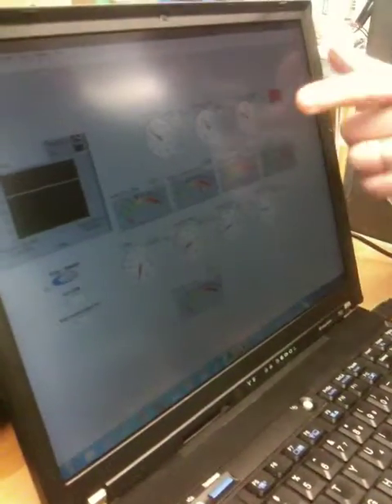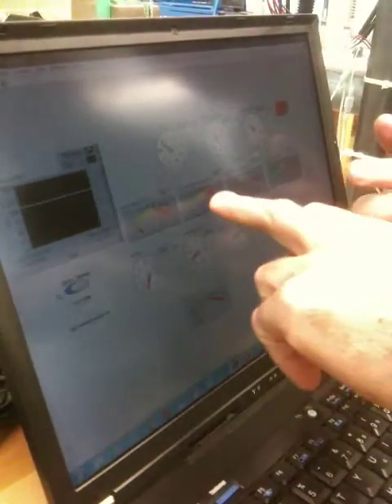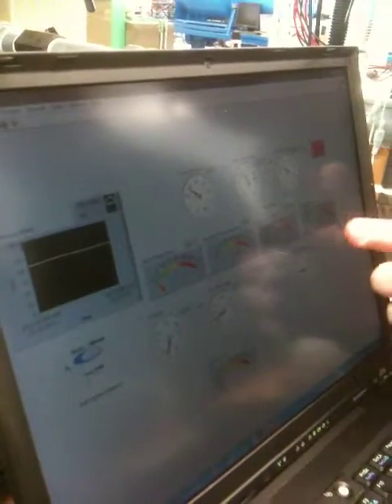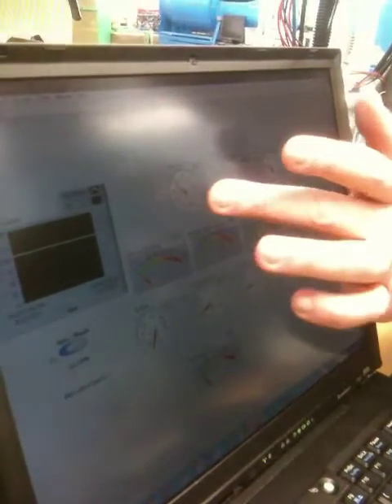So your flow rate is, let's see, magnetic flow meter, yeah. So it's 110, yeah, you can see the number there. 106, and then here's the pump pressure difference, so it's, what, 13.5 psi. Right now we don't have any sort of file saved, so you just got to take your data points by hand. So you just read off of here, get what you think it is, and so here's one point, 108 gallons per minute and so many psi, and then you start to close that valve until you get it all the way closed.